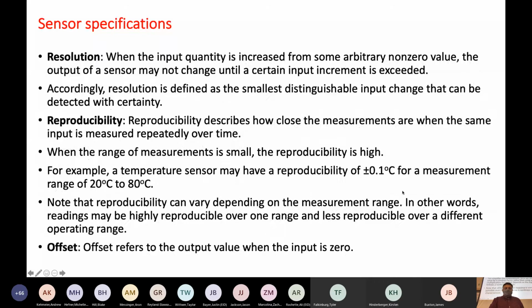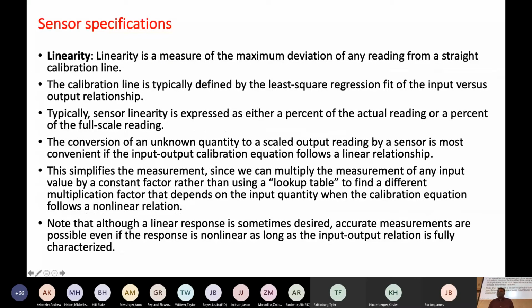So linearity is a measure of the maximum deviation of any reading from a straight line calibration. So we always try to do calibration, where we know that we give a certain input and we get a certain output. In that way, we can create a calibration curve. Now if we put something into the sensor, we can go back and see what that output is. Or if the sensor is outputting something, we can go back and see what the input should be for getting that output. So that calibration line is an important aspect.